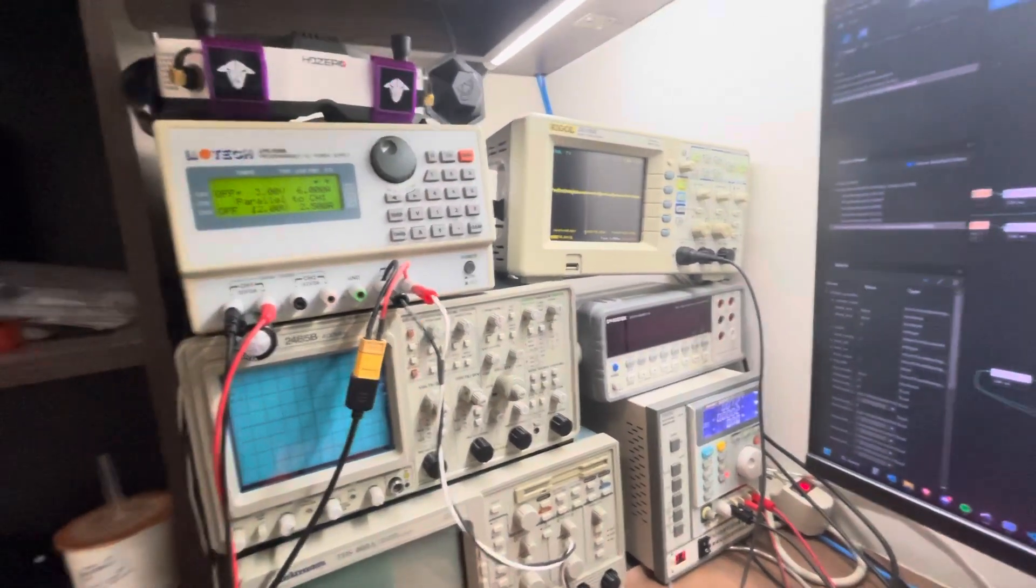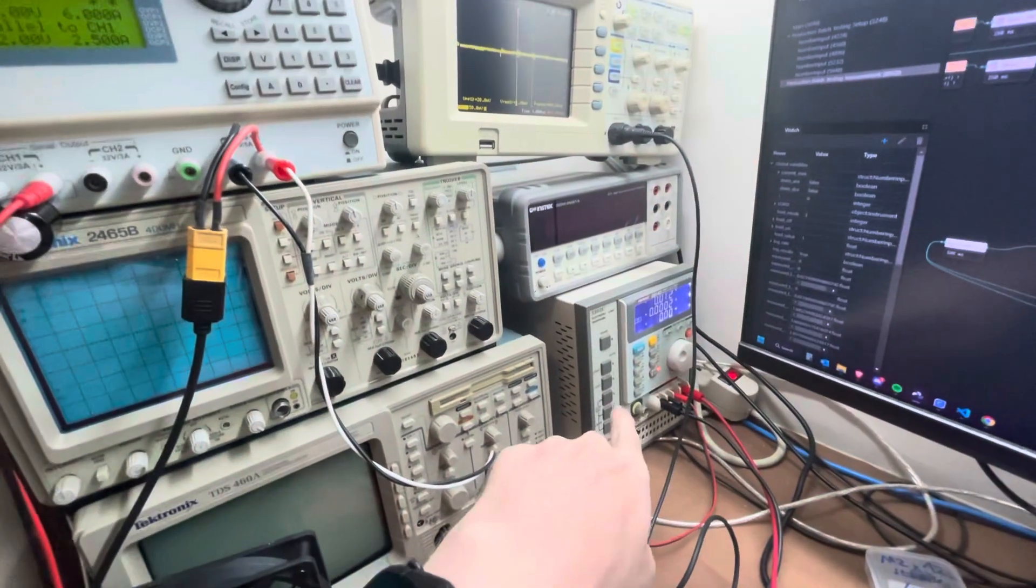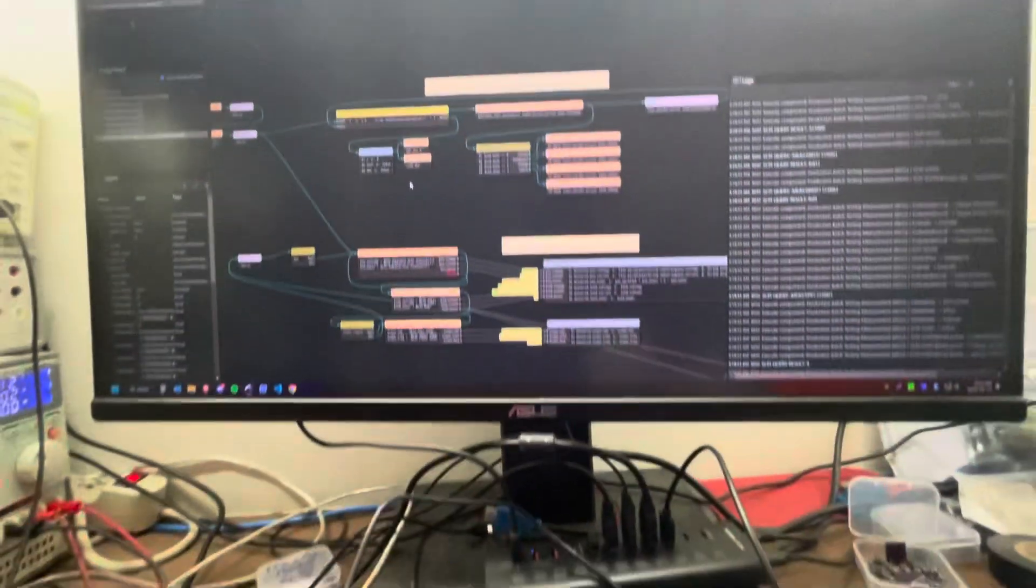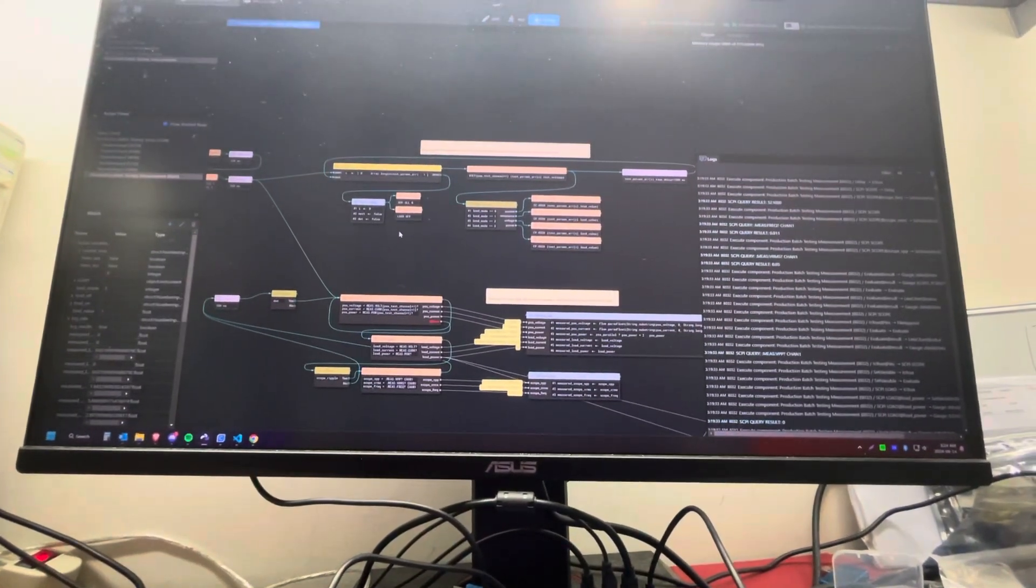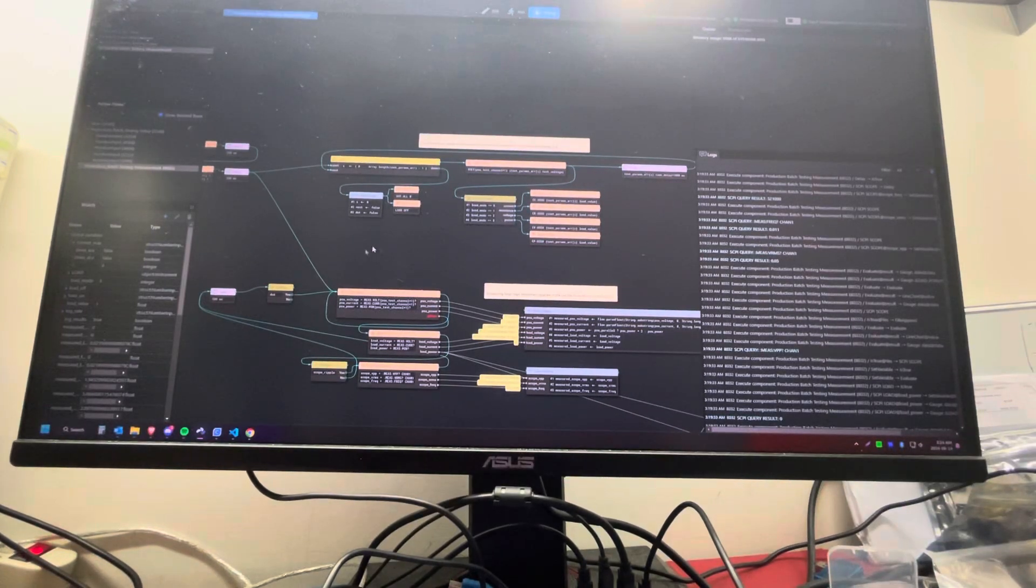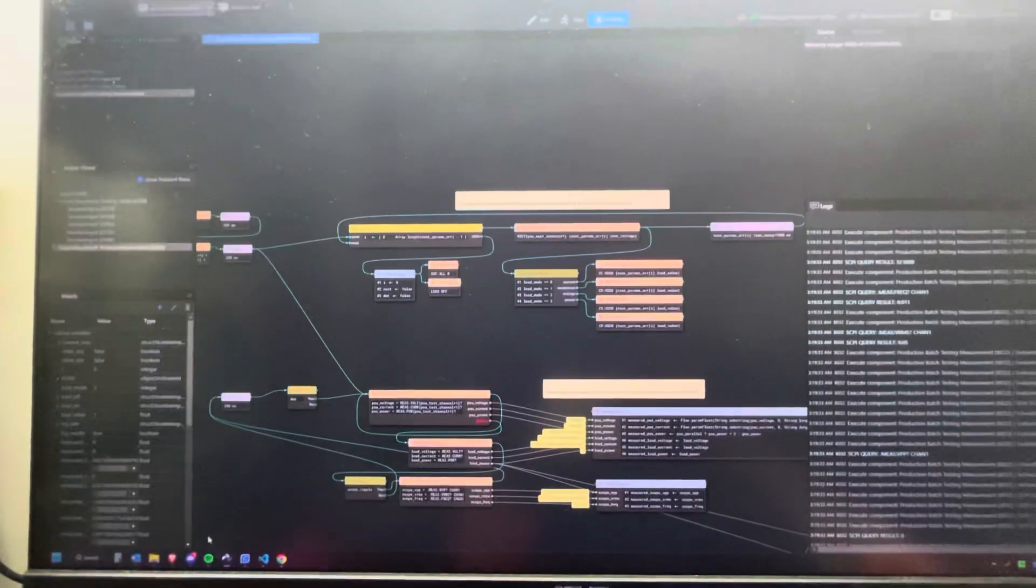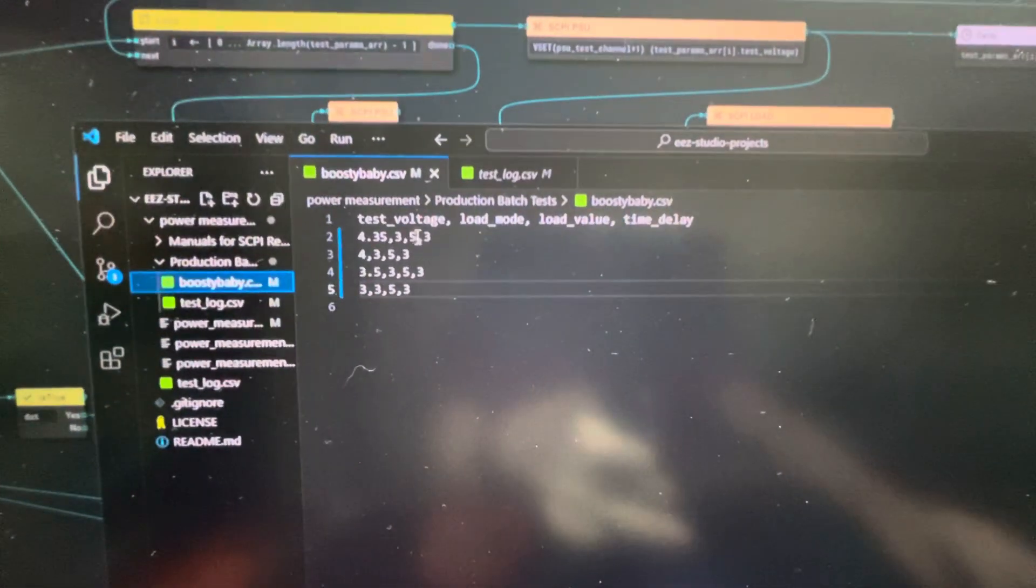That's a communication protocol for some of the instruments. Some are connected through RS-232, some over USB. What's important is that this enables me to command these instruments and send queries for measurements. I have this testing protocol here that's basically an array where I set different voltages, different times, and different loads.